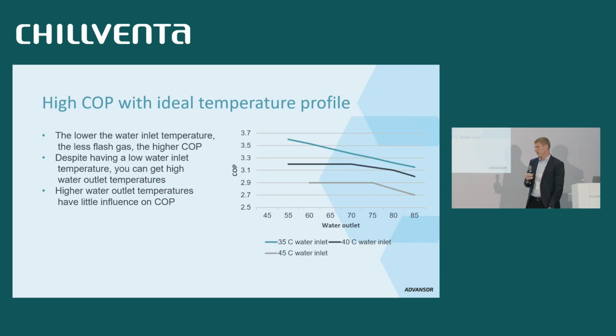When we talk about heat pumps, then of course COP is important. And when we talk about CO2, it's important to understand that things are a bit different from condensing refrigerants. On condensing refrigerants, it's the supply temperature that defines the condensing pressure and thereby the COP of the heat pump. With CO2, that's not how it is. With CO2, it's the return water, so the water coming into the heat pump, that actually defines the optimal pressure we need to operate the heat pump at. So that is clearly an advantage in many situations.